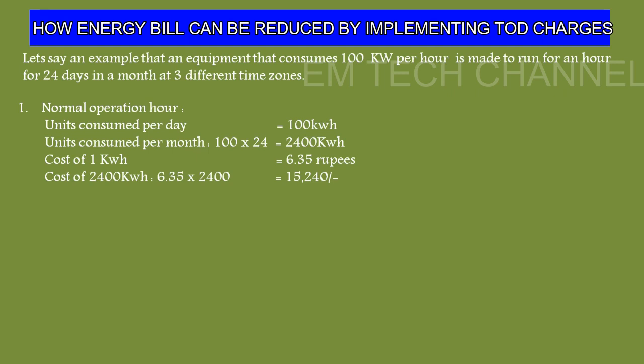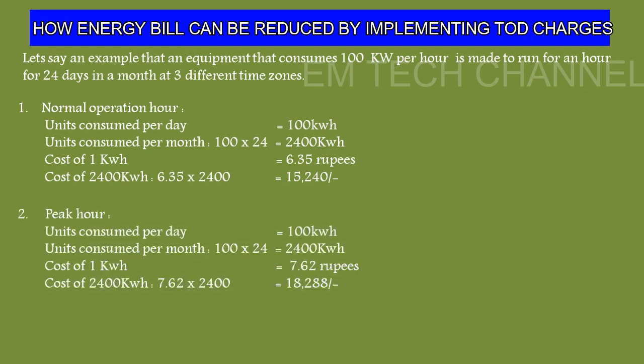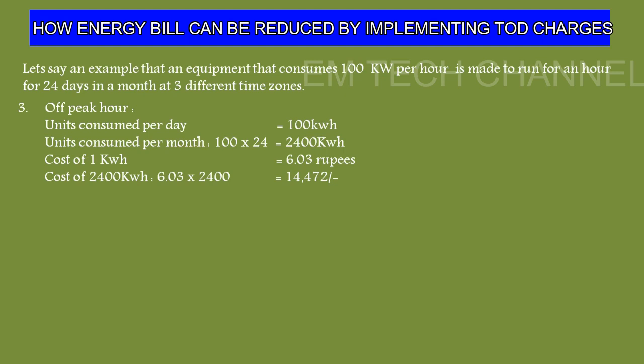For normal operation hour: units consumed per day is 100 kilowatt hours, and per month is 100 × 24 = 2,400 kilowatt hours. At 6.35 rupees per unit, the monthly cost comes to ₹15,240. For peak hour: same 2,400 units, but at 7.62 rupees per unit, the cost comes to ₹18,288. For off-peak hour: same 2,400 units at 6.03 rupees per unit — with the government's 5 percent discount on normal charges — the cost comes to ₹14,472.